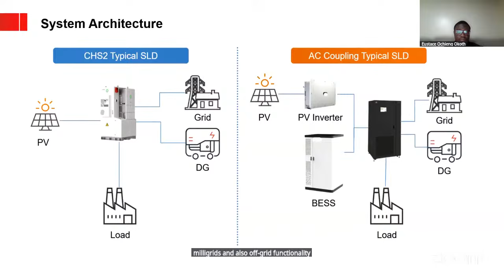When designing, one key thing to look at is redundancy, which you achieve by working with modular systems. Most technology, even from the presenters, is now coming in containerized solutions broken into smaller units that can be scaled up for future capacity expansion. Having redundancy means that even if one system fails, it's very easy to still run your solution comfortably, because its effect is very little.